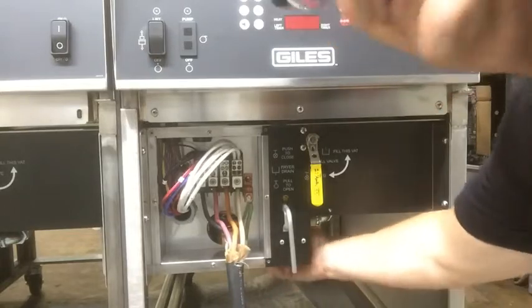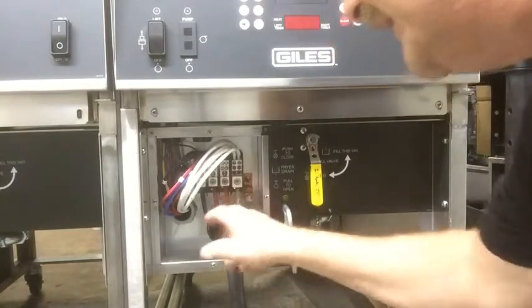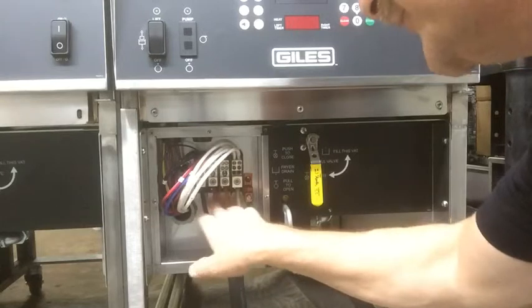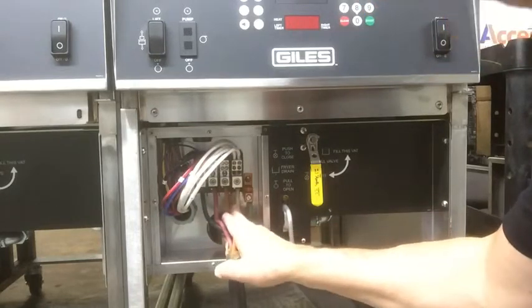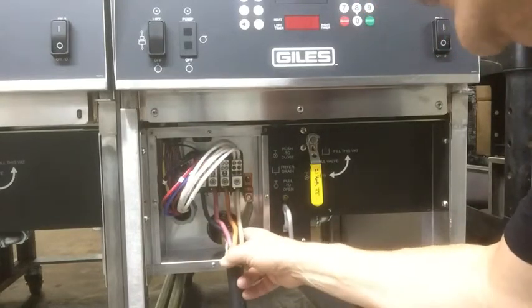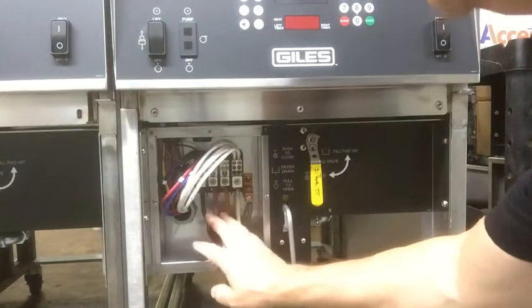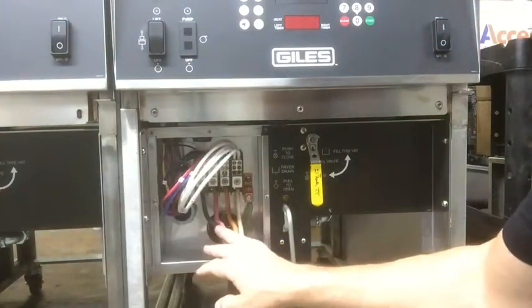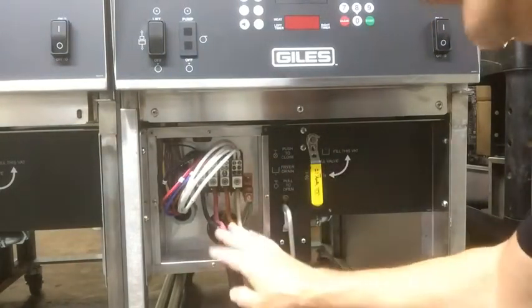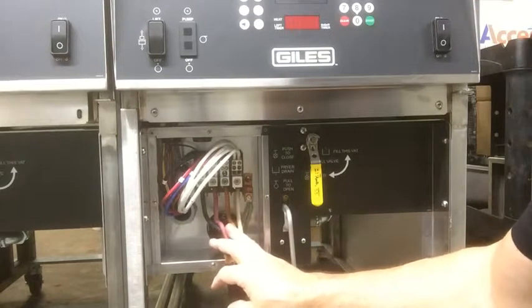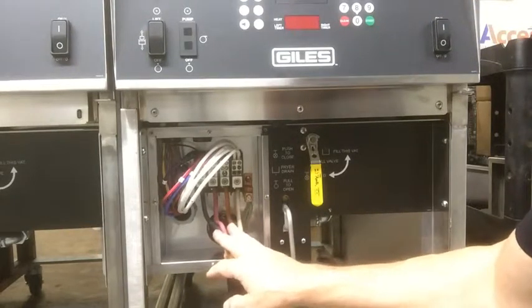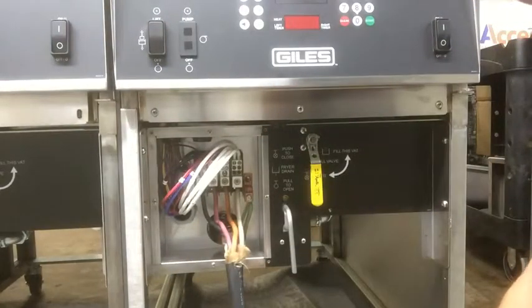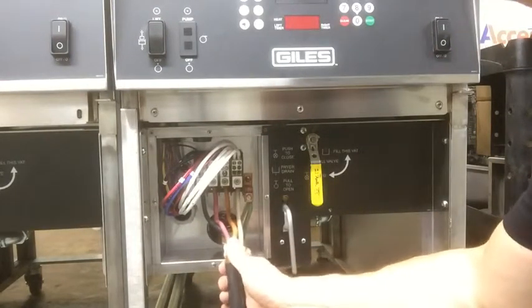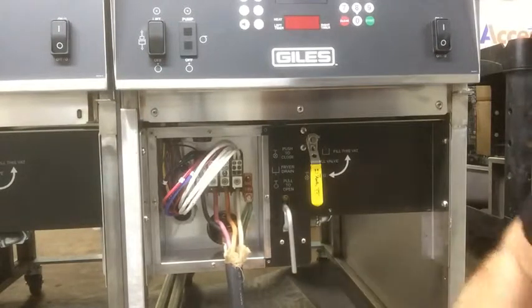So all incoming voltage comes in from the back of the fryer, feeds into here. You've got your 3 hots, your neutral, your ground, and that's all you need. You need that for each one of the fryers, all 3. So you're going to have 3 pulls of power, 3 circuit breakers feeding this bank of fryers. And then of course there's a cover that goes on here to cover this when we're all done. Like I say, we've got it temporarily wired in right now, so just to test everything.